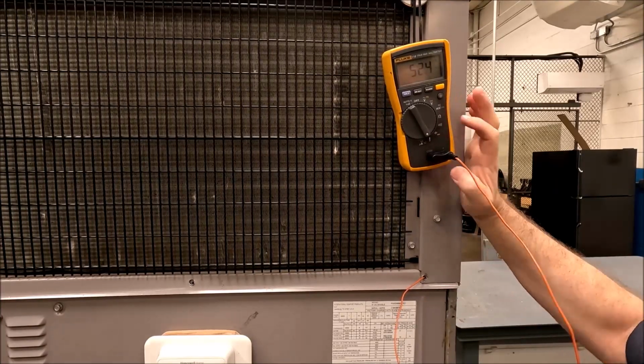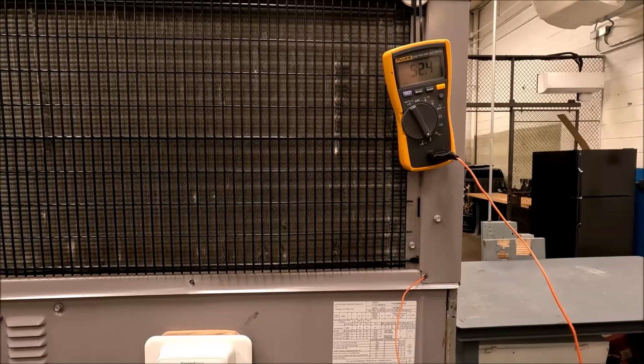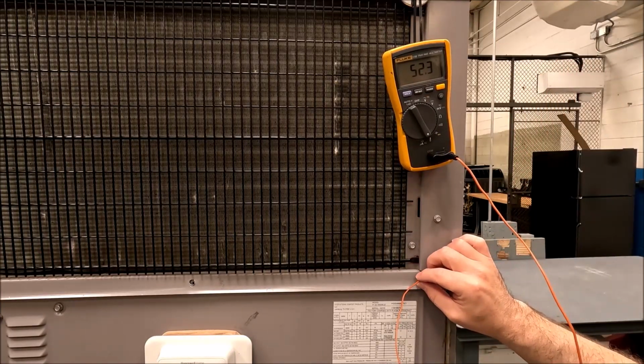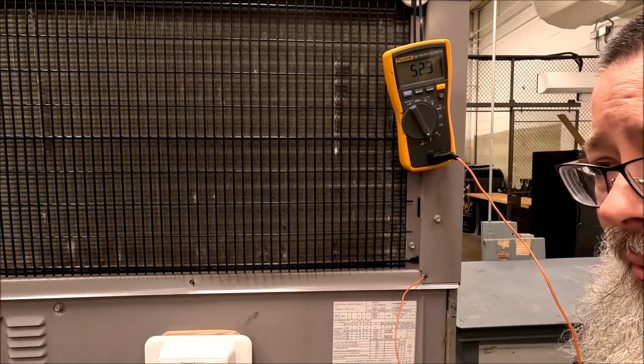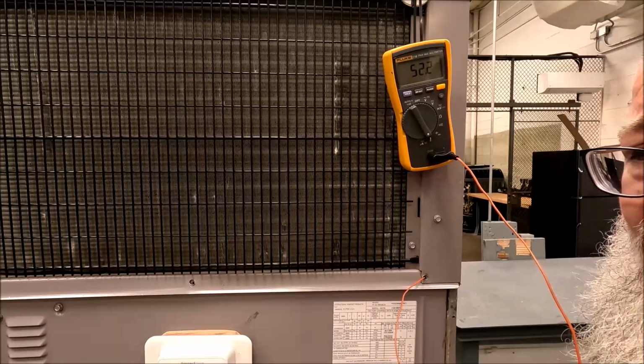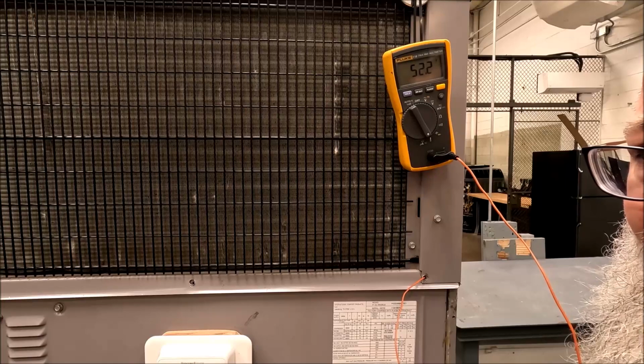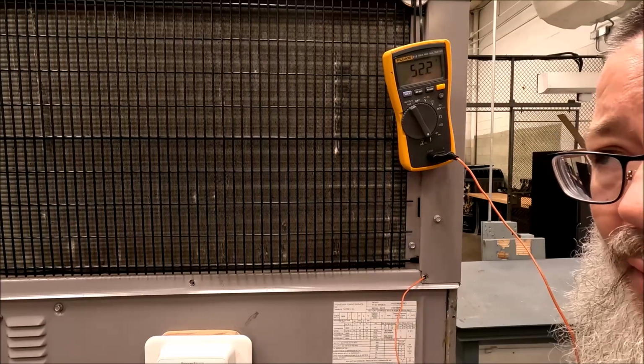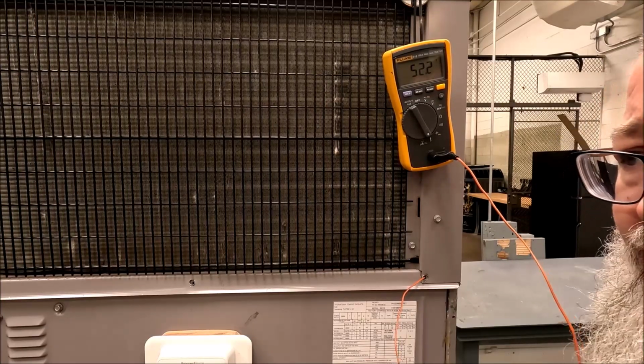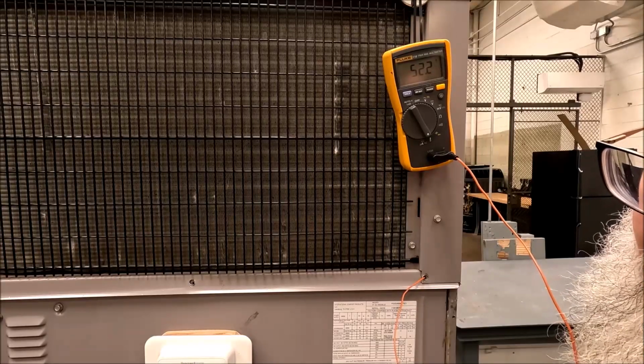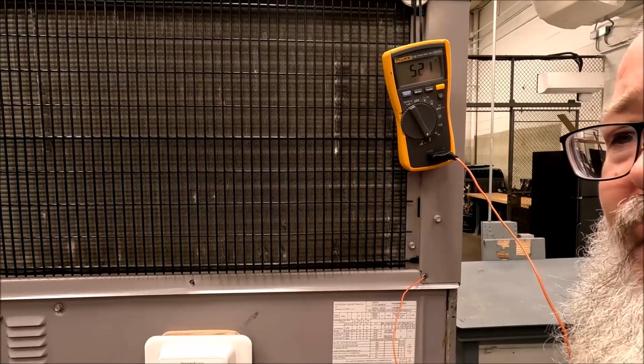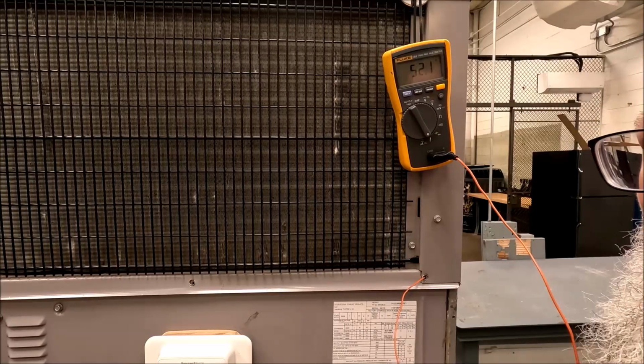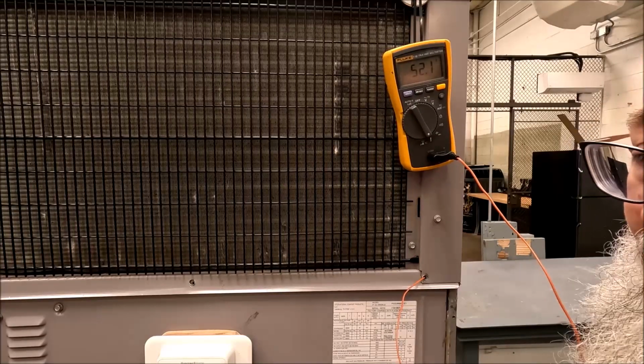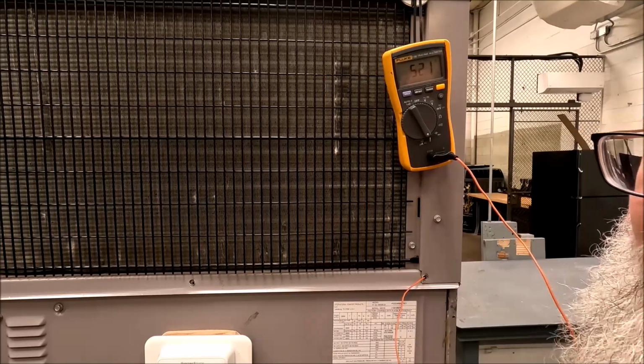Yeah, we'll call it at 52. So that's how I would, on a package unit setup, look and realistically get the numbers. Package units are fairly easy. Split units, heat mode, cool mode, if it's a heat pump, you just got to watch where you put your stuff. It's not always where you put your gauges that you take the line temperature of that spot.